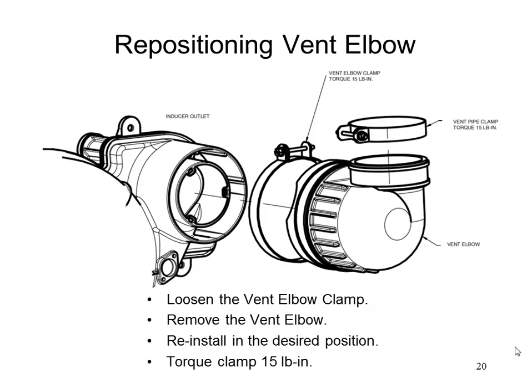There shows you a little bit better blow up of what that elbow looks like. So this is the elbow here. It's got little grips on it, kind of like an oil filter would on your car, right? So you loosen up this radiator hose style clamp, rotate the elbow 90, 180, or 270 degrees, and then tighten the clamp back down. And that's pretty much it. This top clamp here is for clamping on the PVC pipe.